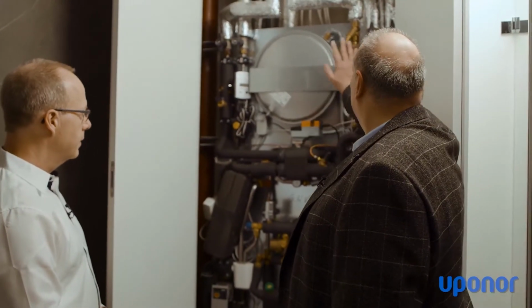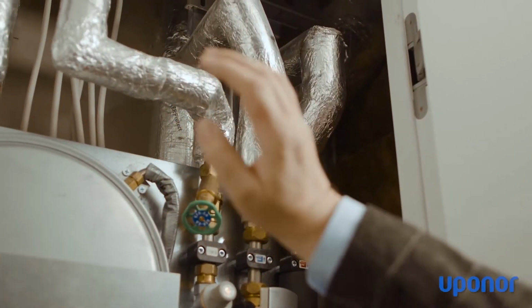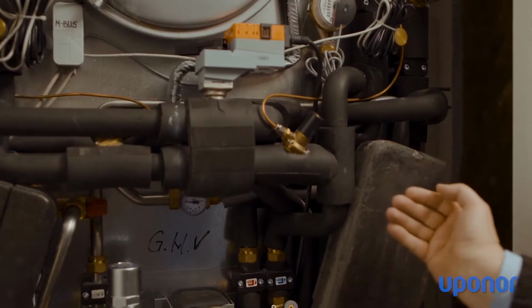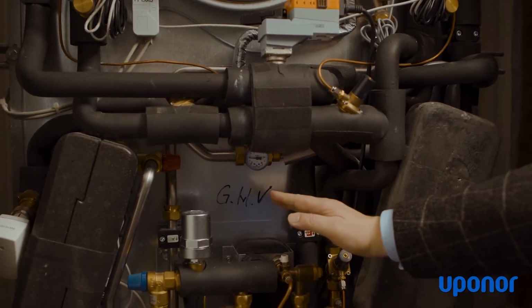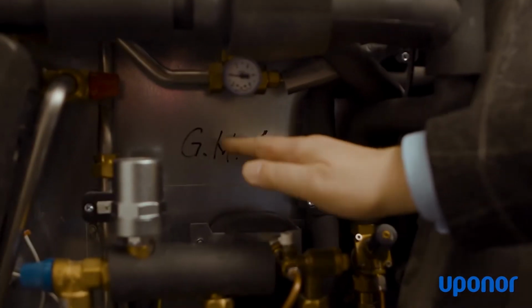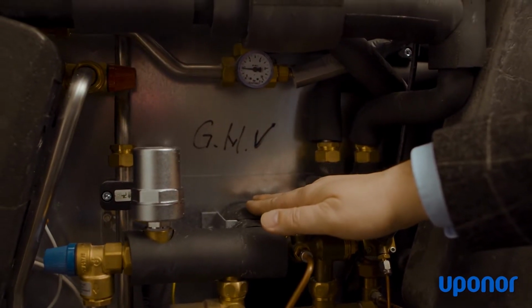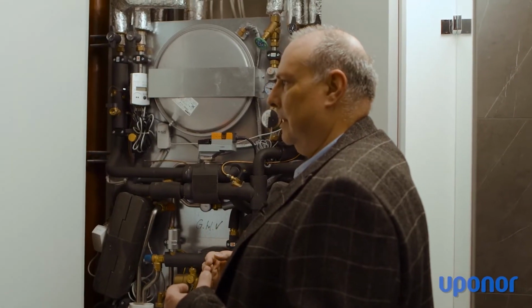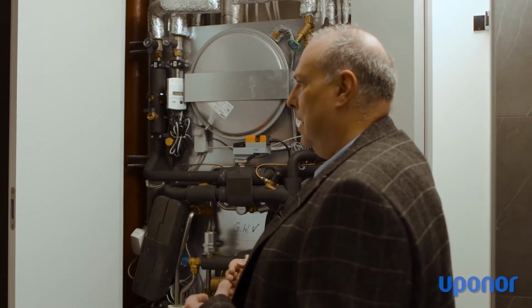So here in this system, we have our heating and cooling supply. We have one heat exchanger for cooling and one for heating, and a third heat exchanger, slightly hidden here, for hot water. We made a conscious decision against using a centralized water heating system. This has advantages in terms of fighting Legionella, as well as instant availability of warm water.